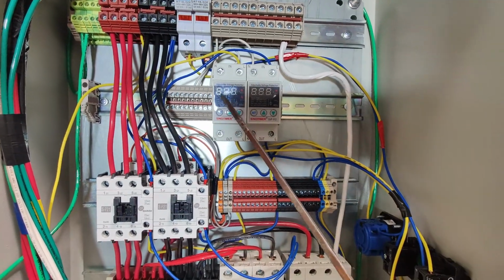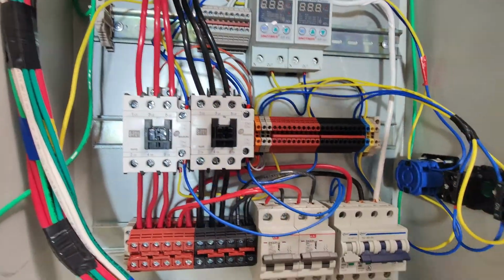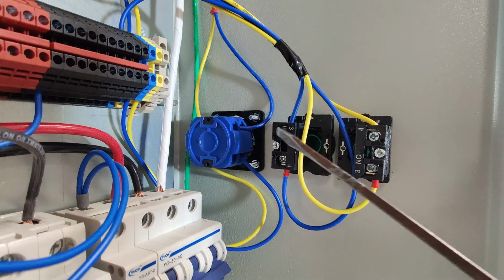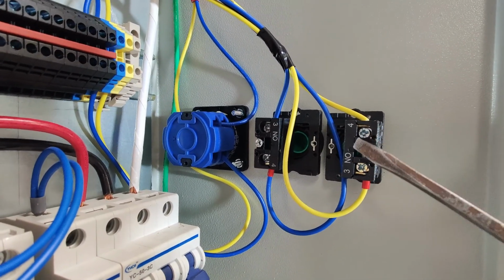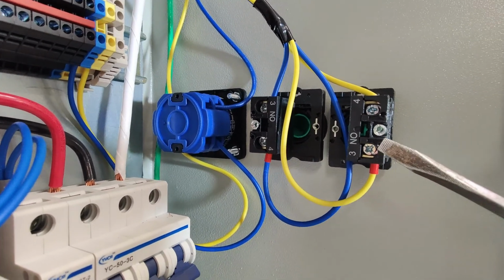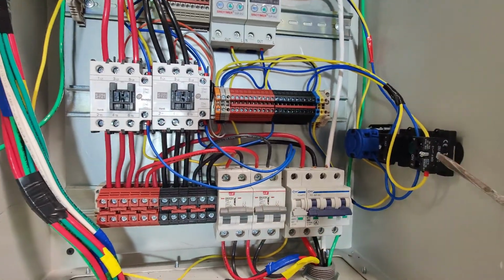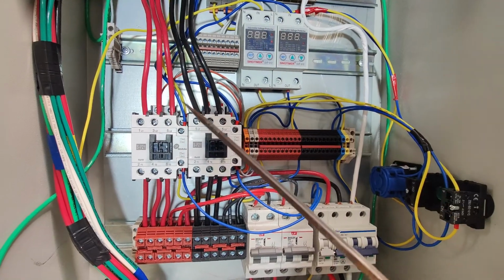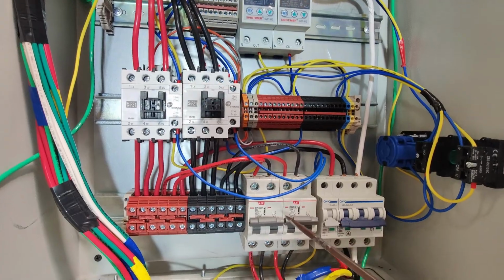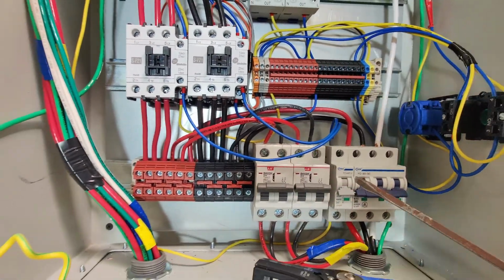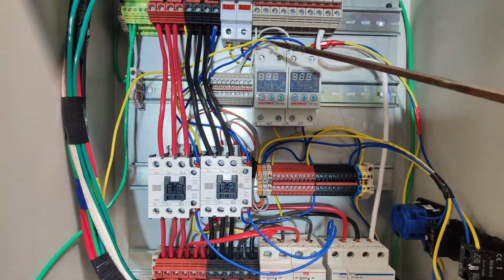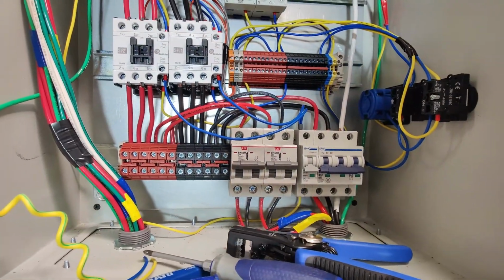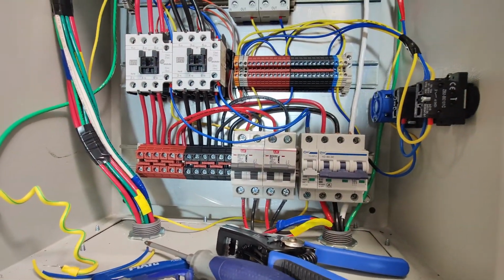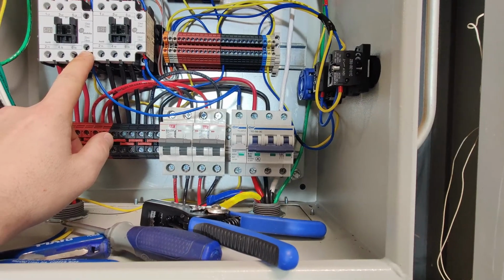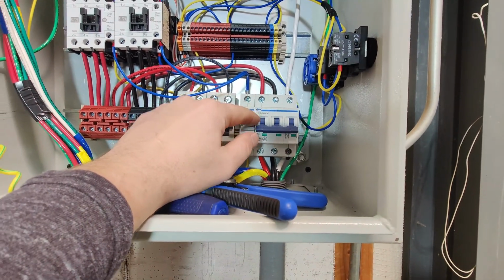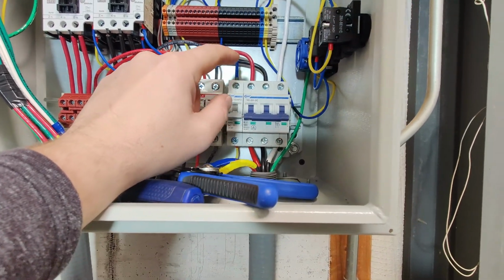So we need to temporarily be able to bypass this mechanism to jump start the system. That's where these two momentary switches come in. We've got this momentary switch here and this momentary switch here. If I could find a momentary switch that would switch two legs at the same time, I would have only put in one. I couldn't, so I put in two. Essentially that allows us to bypass a voltage protection relay to turn the contactors on, allow the voltage to come through, and go down here to each one of our auto transformers. So our auto transformers will start making the neutral leg, which in turn will show up here. However, this might seem similar to the circuit that I had before, but the difference here is that there's never a time period where this system can operate without a neutral leg and then also have this shunt trip breaker not closed. So this not open.